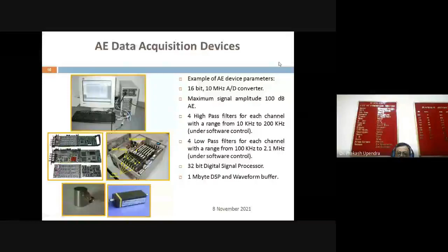There will be an analog to digital converter. This specification may vary; a typical one is 16-bit, 10 megahertz, and the maximum signal amplitude will be 100 dB. This can be varied depending upon the application. There will be high-pass and low-pass filters. Depending upon the application, 10 kilohertz to 200 kilohertz, which is under software control. Then there will be a signal processor, and data signal processing with 1 MB waveform buffer.